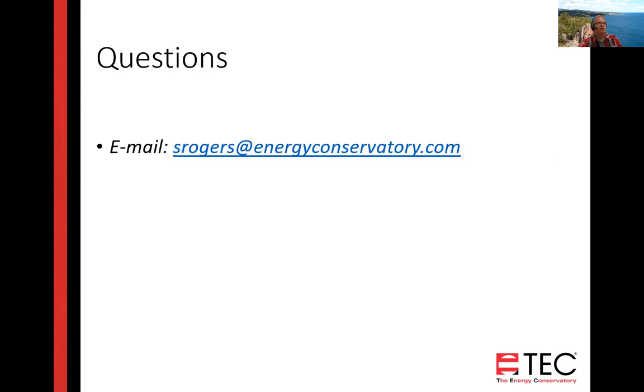Well, yeah. So the thing to consider is what you have to ask. So you're sort of answering the second half of the question. If you balance your house on a certain day, will it be in balance on all other days? Actually, the answer is if the fan curves are parallel of your fan that's pushing the air in and pushing the air out, and if they are entering and exiting at the same level, then it won't matter if they're high or low. But if you are sucking air in at the top and down at the bottom, and you have weak fan curves such that 2 pascals of stack effect is actually going to get you to a significantly different flow on your fan curve, then yes, it will have a small effect.